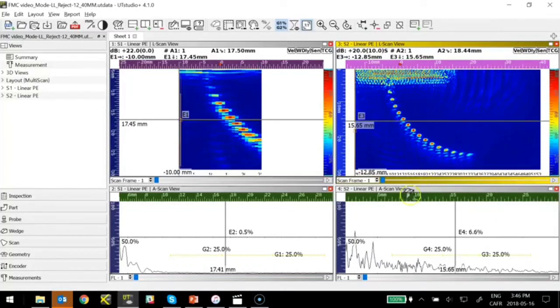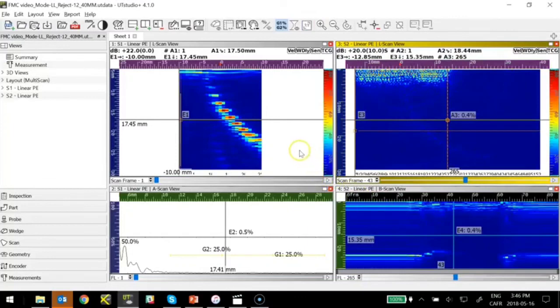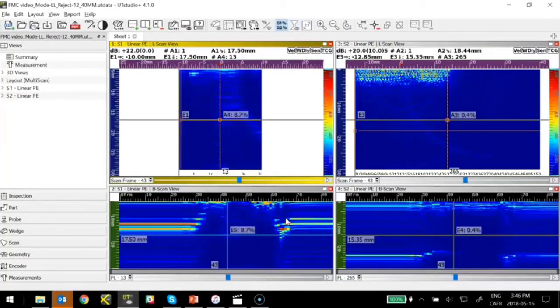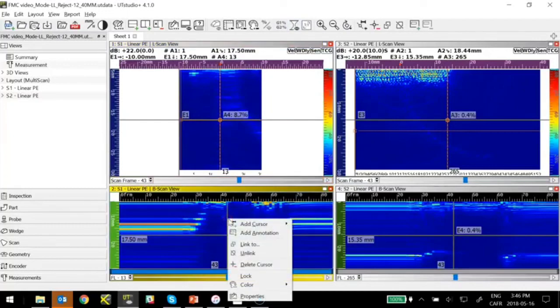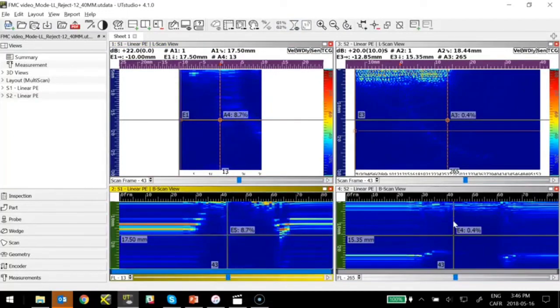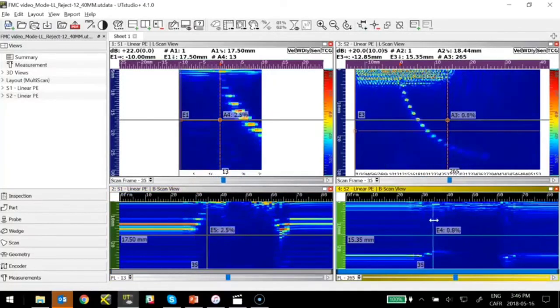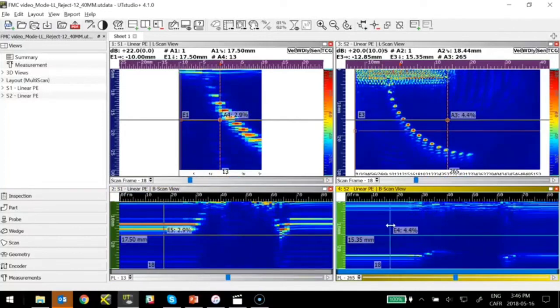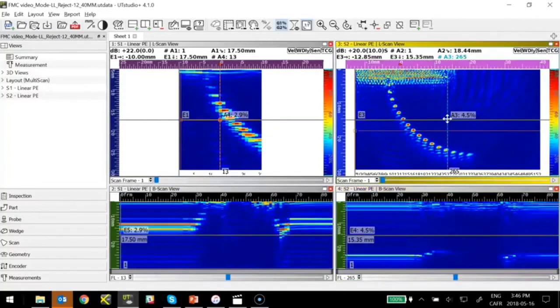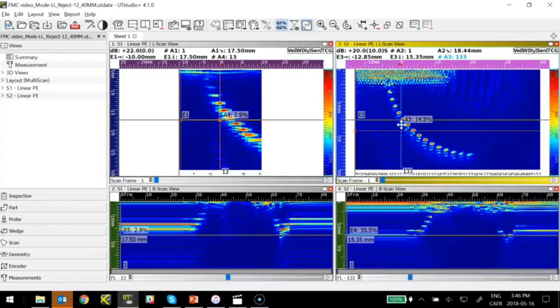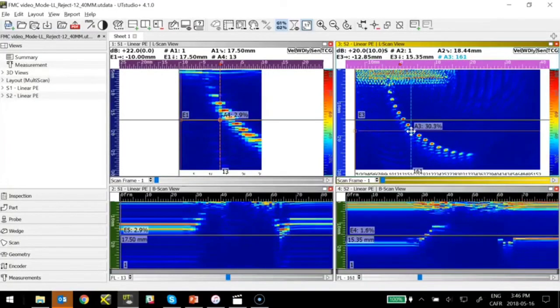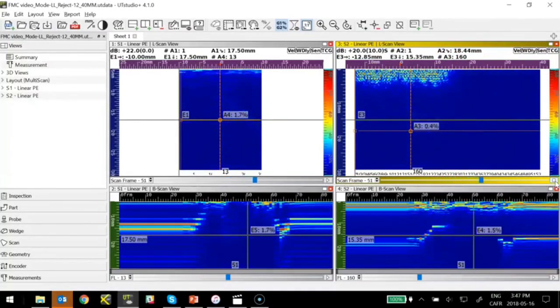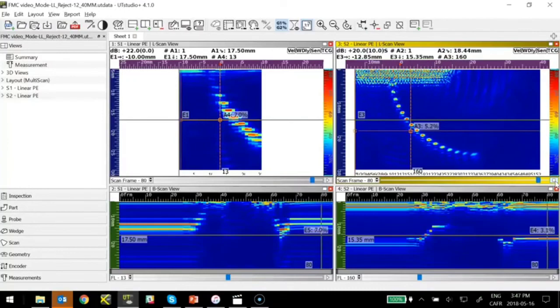Now, an interesting advantage of the Sonatest TFM approach is that all the standard phase array tools like B-scan, TopView, End Views, all the encoded tools that were available for phase array analysis are all available for the TFM analysis. For example, since I recorded concurrently FMC and TFM, but also phase array scan all together, I'm able to synchronize the encoder together, and then when I get over a defect, I will have the exact same position on the phase array scan and the same signal position on the TFM image. The main benefit here is that the user can use code-compliant phase array to call a defect, but add valuable information from a TFM image.